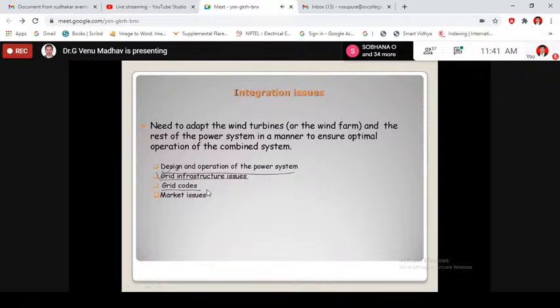The grid code says a wind turbine should never be stopped. Previously, once stopped, reconnecting and synchronizing back to the grid would take 20 to 30 minutes, causing loss of power. Nowadays, if a fault occurs, the wind turbine should freewheel itself instantly. Power may not be generated or given to the grid at that moment, but once the fault is restored, it must reconnect immediately with no time lag. This is achieved through fault ride-through technology, though it may increase the cost of the wind turbine.